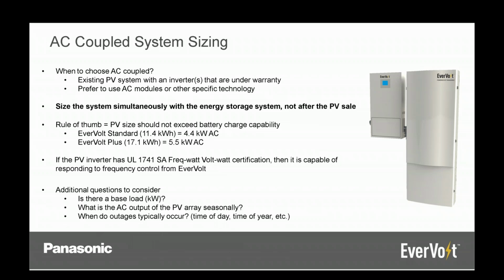Now there are a few additional considerations, more intermediate or advanced installer-type questions, when designing an AC coupled system. Is there a base load? For example, there's generally always going to be some lights on or some heavier usage loads, like a refrigerator kicking on during the day, or a great example, a hot tub that's kicking on every hour. You can plan for that and size the PV array to be able to supply that as well. You also want to consider what the AC output of the PV array is seasonally.